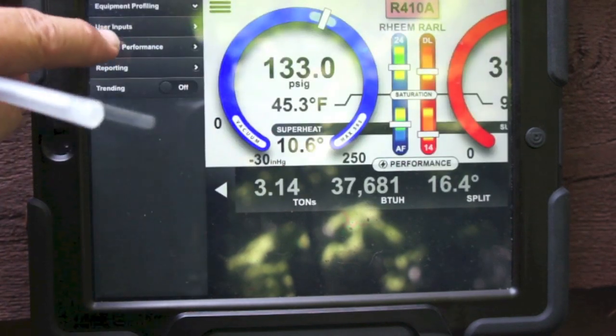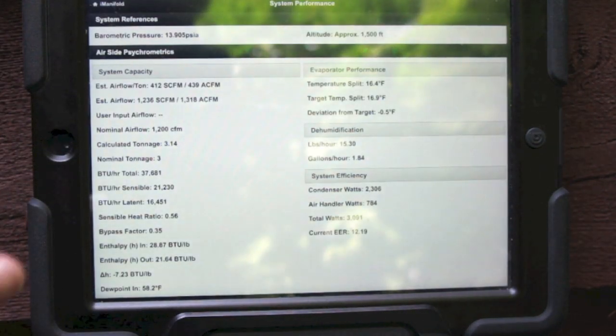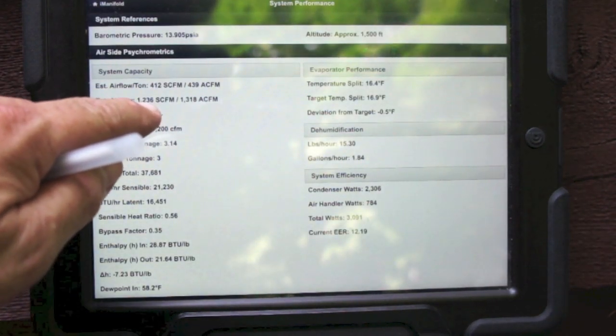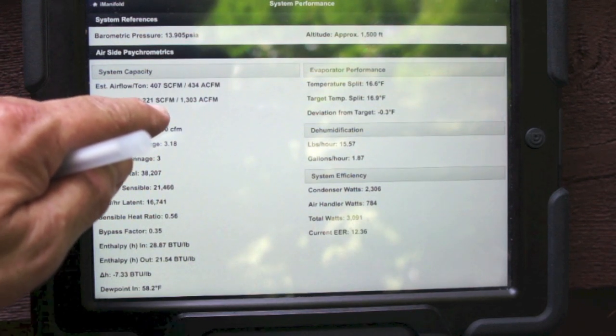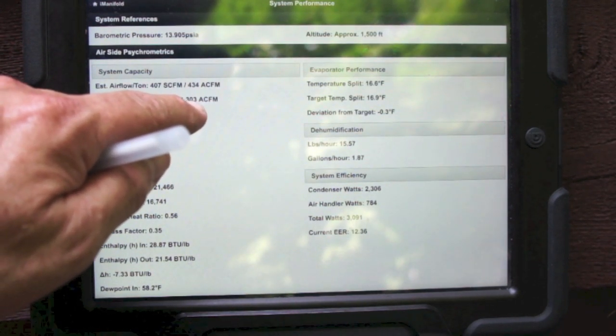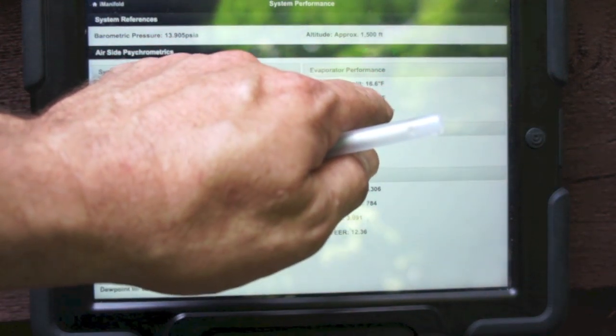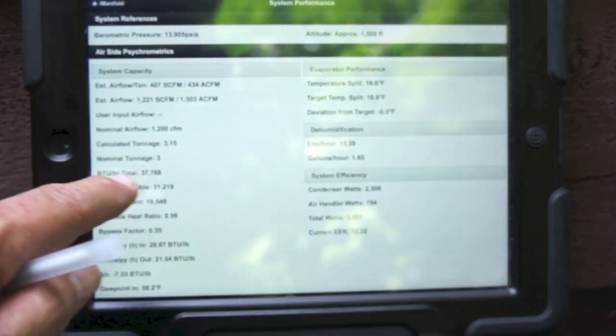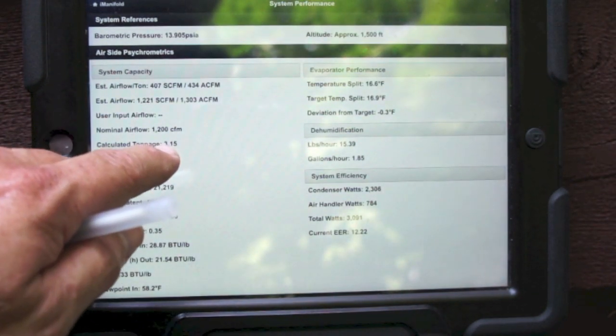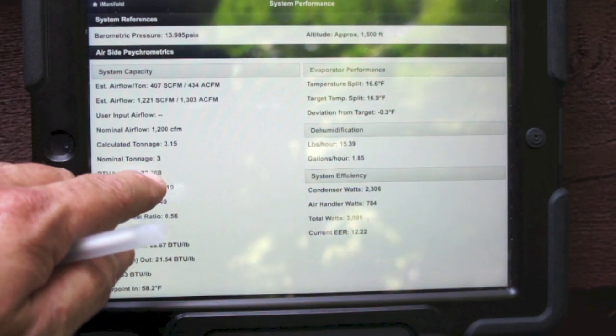So let's go ahead and we're going to go to system performance for a second. You can see that my estimated airflow is 1221, standard CFM 1303, actual CFM. We're at our temperature split at 16.6. Our target is 16.9, so we're 3/10 away on our split. Our calculated tonnage is 3.15, our nominal is 3.